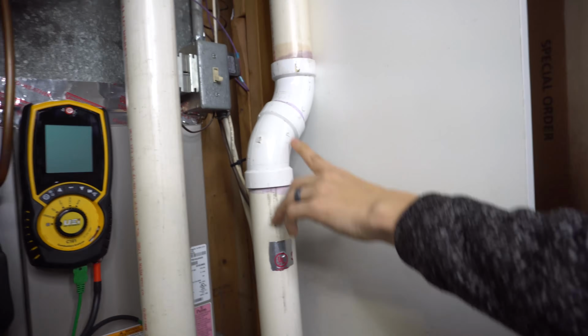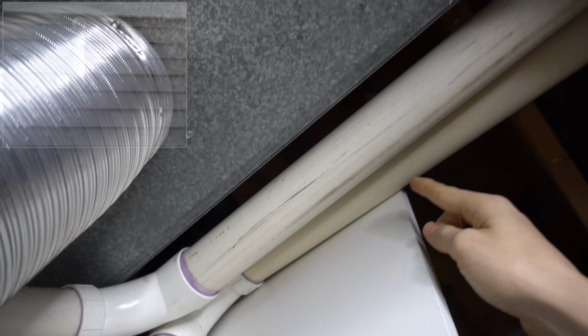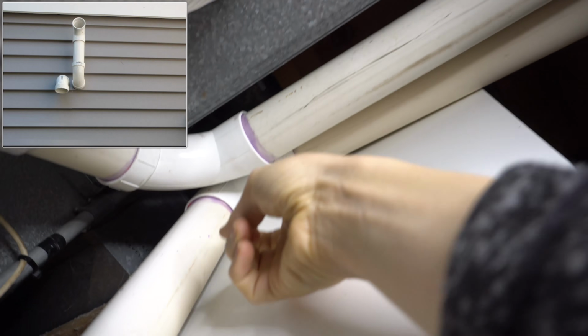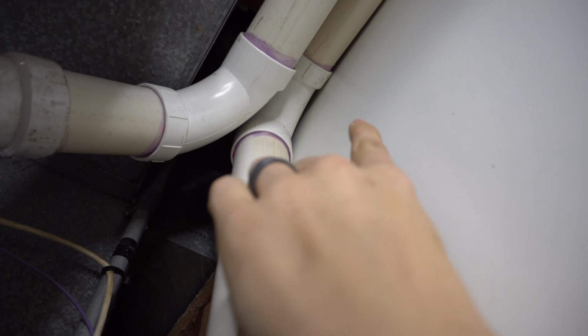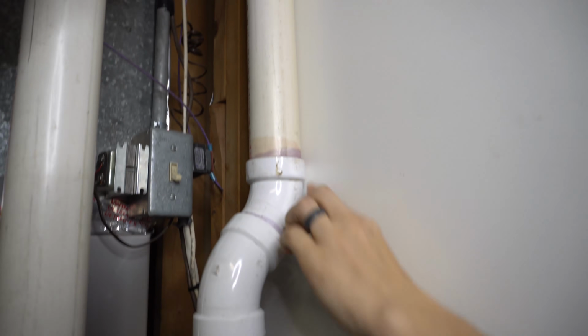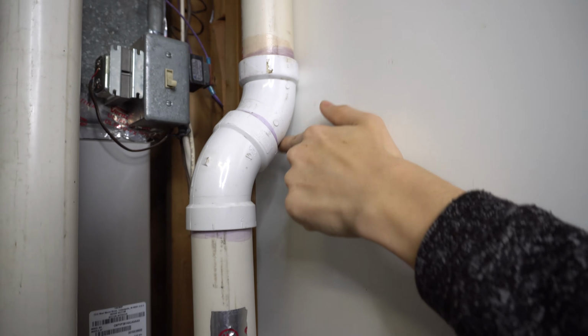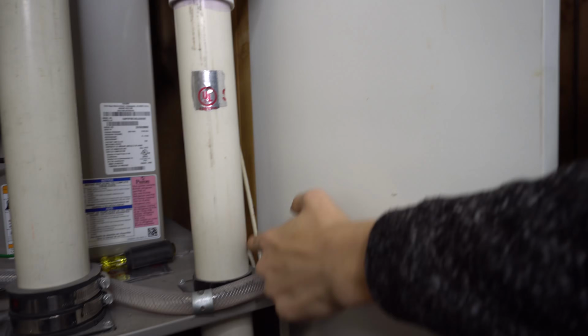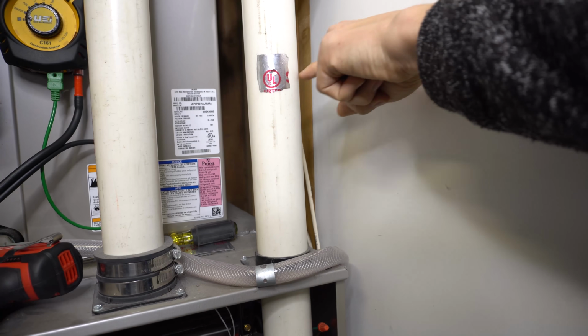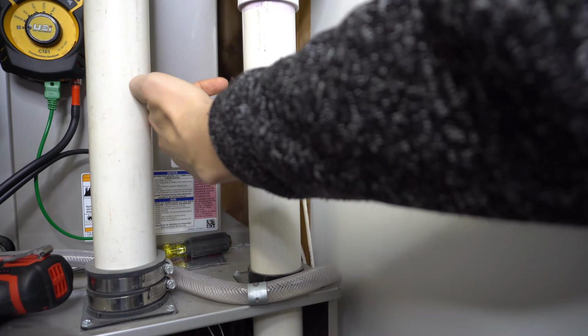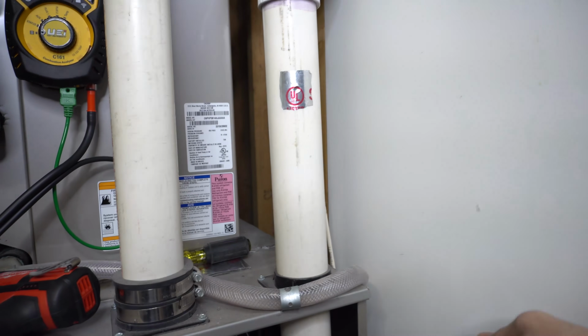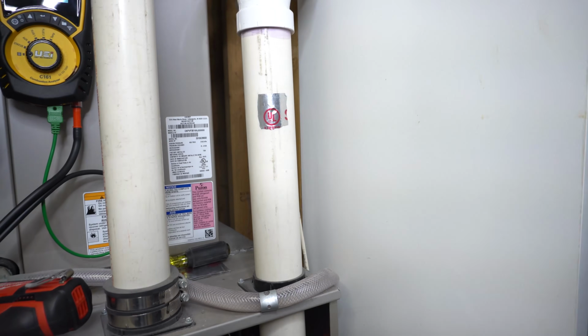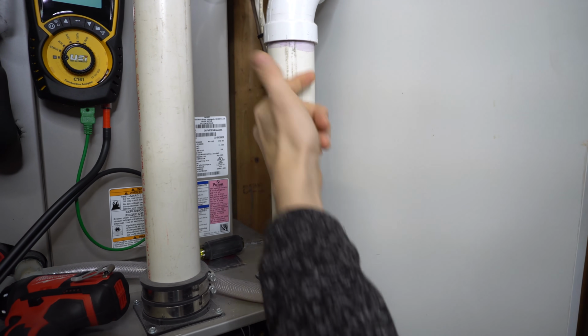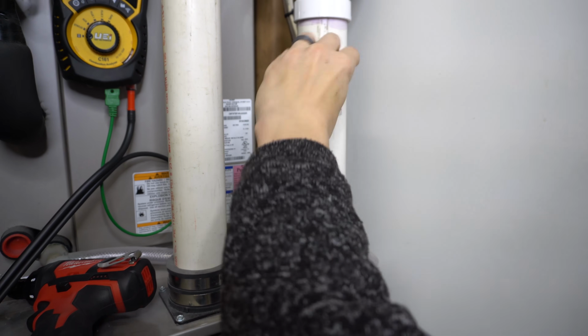So if we look further upline of the exhaust pipe, right here, it just basically goes outside and out the wall, but it goes into a 90-degree bend, and it turns down, which means the water flowing down is going to be going down this side of the pipe, most of it. So it goes down, and then if you just follow it, it'll go down on this wall, and it'll trickle mostly on this side. So you definitely don't want to drill a hole on this side. In this case, you would want to drill the hole somewhere on this side, and preferably, maybe like a foot away from the furnace itself. This is a pretty good spot. So in a nutshell, you just don't want to drill a hole where the water is going to be running down. So let's take this piece of tape off.